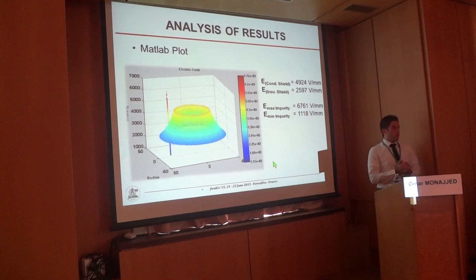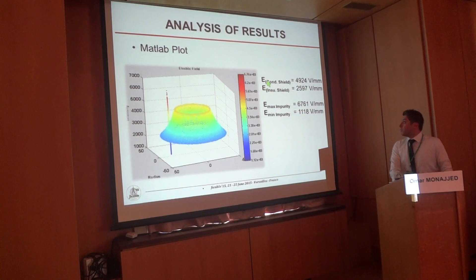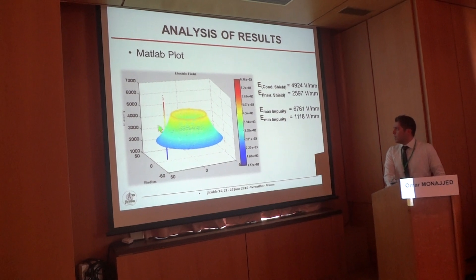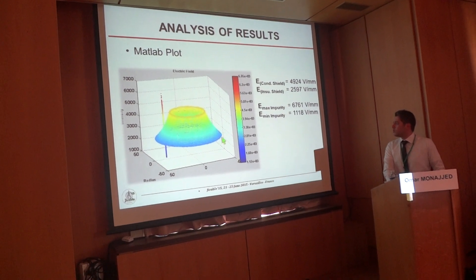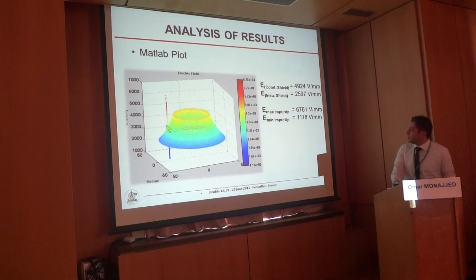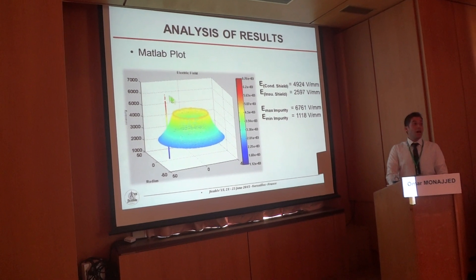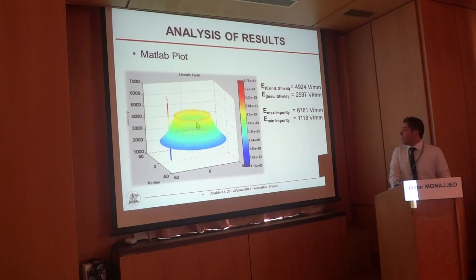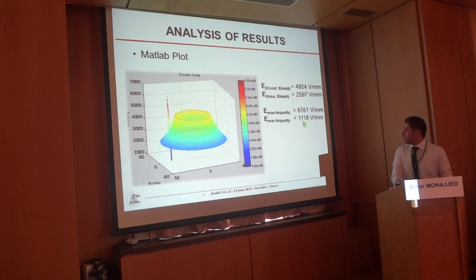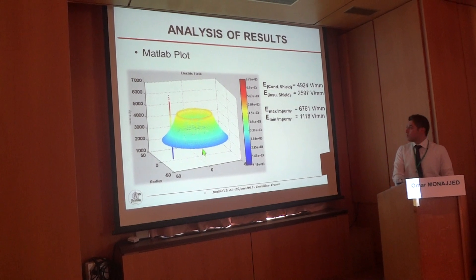To better understand, we apply the results in MATLAB in 3D. The conductor shield stress is 4924 V/mm. The outer semi-con stress is 2597 V/mm. At the impurity, we have a maximum stress of 6761 V/mm, which is even higher than the stress at the inner semi-con. Also at the impurity, the minimum stress is 1118 V/mm, which is even lower than the stress at the outer semi-con.